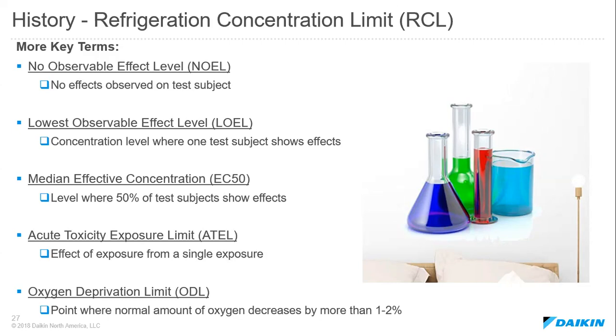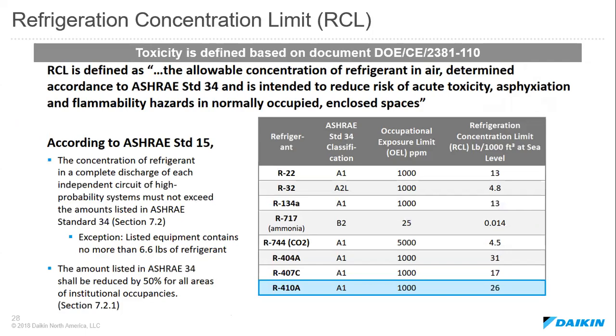So, as a statement of fact, our air tends to be around 20.8 to 21% oxygenated. And so when we drop below that level by more than 1 to 2%, that's the oxygen deprivation limit. So, like I said, toxicity is defined in that document written and published by the Air Conditioning Refrigeration Association. RCL is defined as that allowable concentration of refrigerant in the air that's determined in accordance with ASHRAE 34.